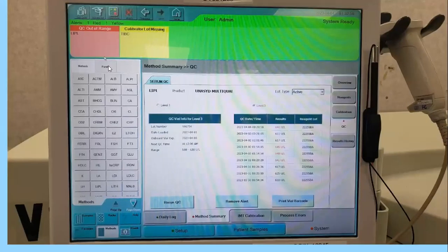Alright, so QC has finished running, and we only had one that was out of range. So how you fix or rerun QC is what you're going to do is click on the little red box that says QC out of range, and it will pull up the QC level that is out. So the QC that is out is one of our lipid tests, and it was on level 3. So it says QC vial info for level 3 on the left.